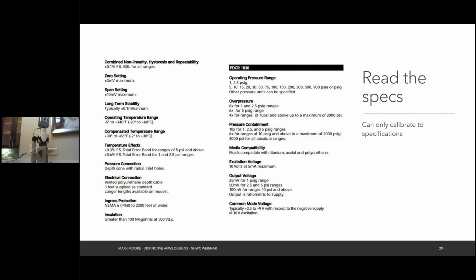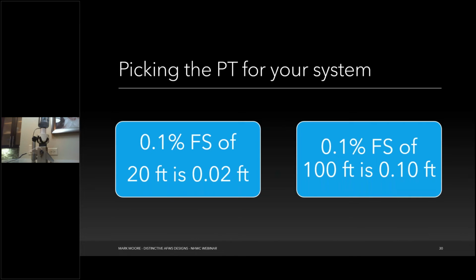All right, let's take that apart real quick. Combined nonlinearity, hysteresis, and repeatability. Well, that just means that it's combined error. We'll talk about what those mean in just a second. It's plus or minus 0.1% FS. FS stands for full scale, so it's plus or minus 0.1% of the full range of the PT. And BSL stands for best straight line for all ranges, which is really just saying it's combining that nonlinearity, hysteresis, and repeatability. So what this is actually saying is that it's 0.1% of the range of the PT, and that's how accurate it is. Well, that means you have to pick the right PT for your system.